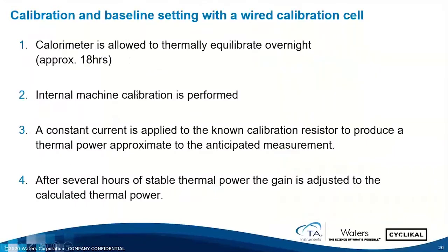All right, calibration and baseline setting with a wired calibration cell. Again, this slide is meant to imply that inside our calorimeter we now have a calibration cell. For every type of cell we've used, coin cell, pouch cell, or cylindrically wound can cell, we have calibration cells which consist of the chemistry of the materials that exist in the cell we're going to do experiments on, but it does not have any electrolyte. So the cell is electrochemically dead. In the cell is placed a known resistor connected to the positive and negative so that it's actually shorted through this resistor. And this allows us to apply a current to it.